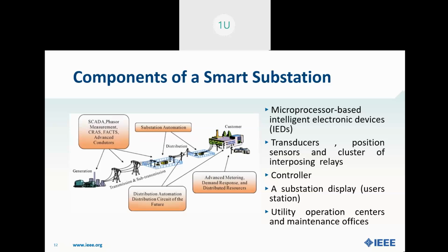Going back to our point, that is utility operation centers and maintenance offices. Most of the smart automation systems connect to a traditional SCADA system master station, serving real-time needs for operating the utility network from one or more operation centers. Similarly, smart substations also incorporate a variation of the SCADA remote terminal unit for this purpose, where it is possible to support multiple clients simultaneously.